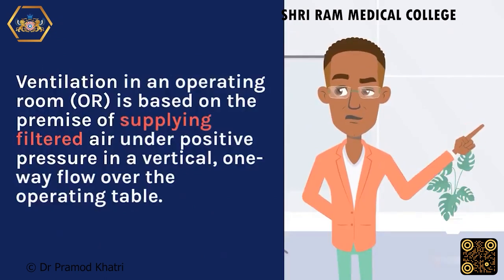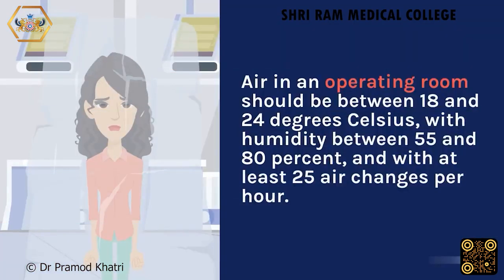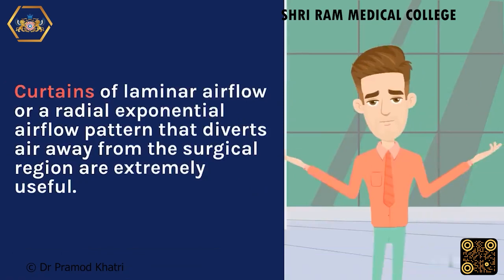Ventilation in an operating room, or OR, is based on the premise of supplying filtered air under positive pressure in a vertical, one-way flow over the operating table. Air in an operating room should be between 18 and 24 degrees Celsius, with humidity between 55 and 80%, and with at least 25 air changes per hour. Curtains of laminar airflow or a radial exponential airflow pattern that diverts air away from the surgical region are extremely useful.